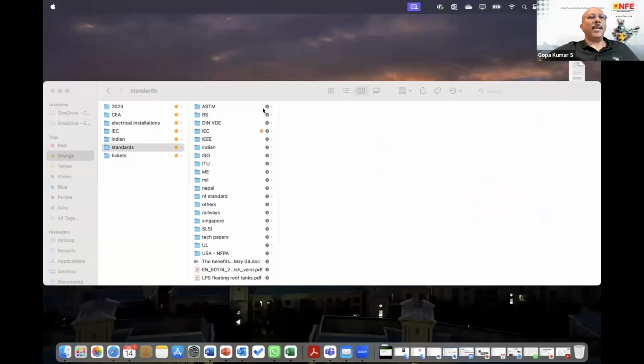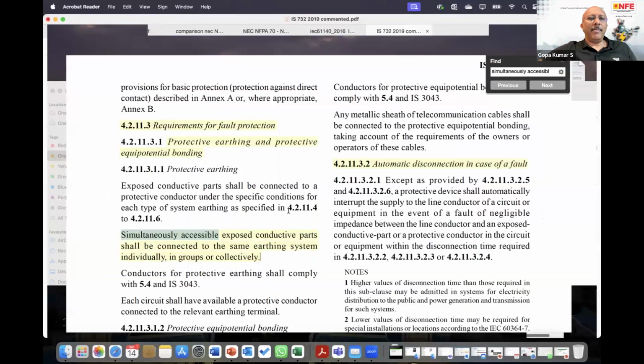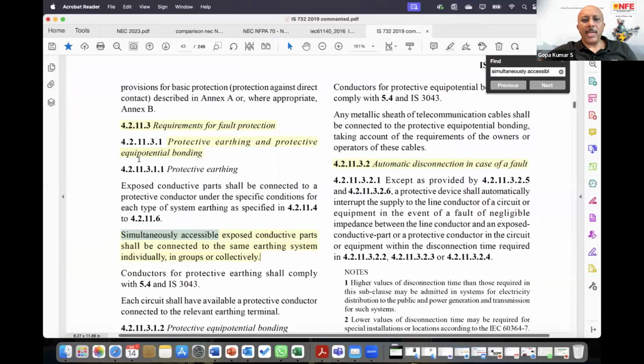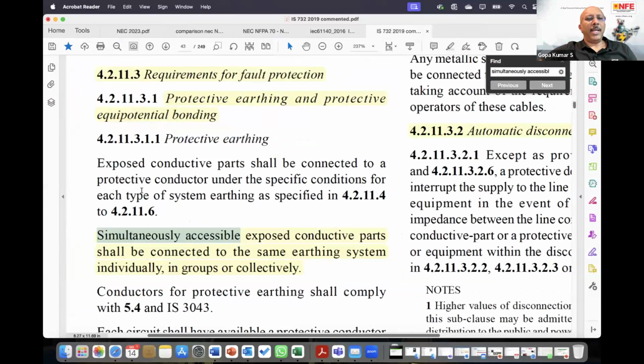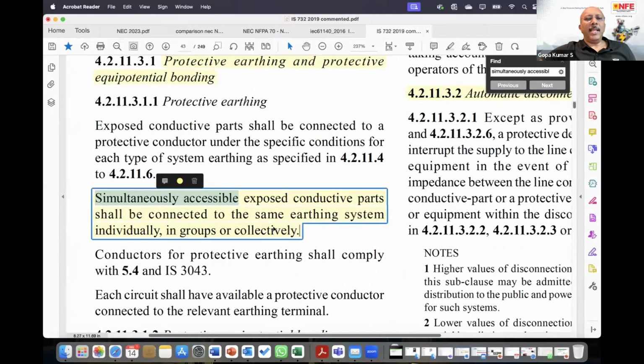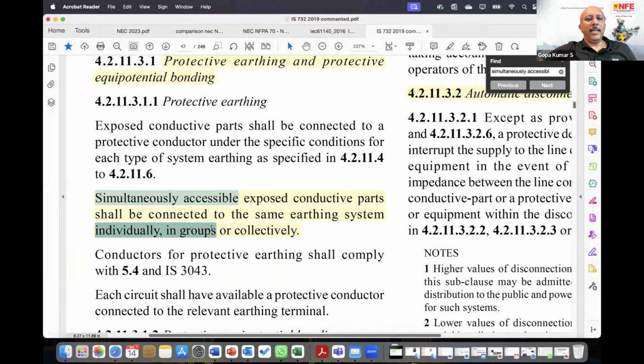Let me share the screen again. Are you able to see the screen? As you started with the earthing, I am showing IS 732, which says simultaneously accessible exposed conductive parts shall be connected to the same earthing system individually, in groups or collectively. That means class 1 equipment can be connected to the same earthing system, common for one building, individually, in groups or collectively.